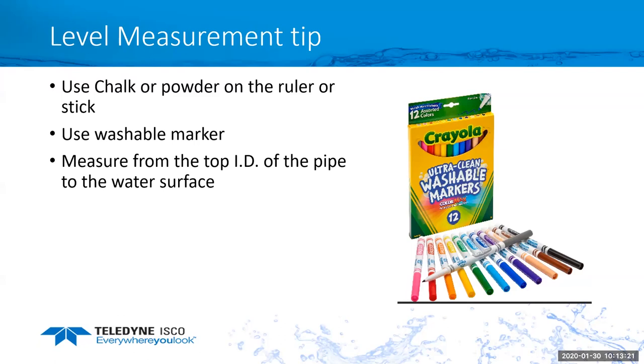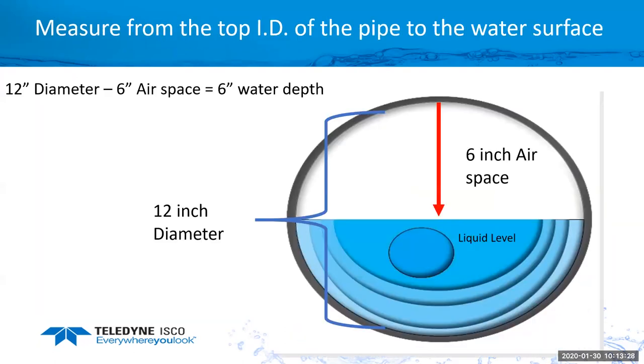Another option, especially if you have high velocity, is to measure from the top of the pipe. So in this example, what we'd do is measure the ID of the pipe. In this case, it's 12 inches. We'd have 6 inches of airspace. So I'd take 12 minus 6, and that gives me 6 inches of water depth. So I would then calibrate my level to 6 inches. This comes in really handy if you have high velocity, because if you put a ruler in an application that has like 5 feet per second velocity going through there, it's going to rise up on your ruler and it's going to be difficult to get an accurate level reading, because it's going to rise up on the ruler anywhere from a quarter inch to 1 or 2 inches. And at that point, it's just kind of guesswork as to what the actual level is. So this approach may be more accurate for you.